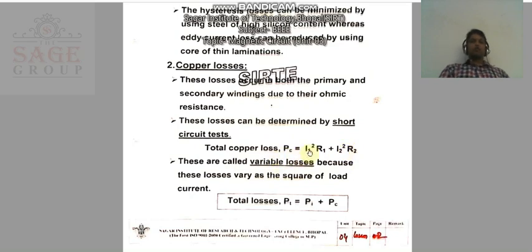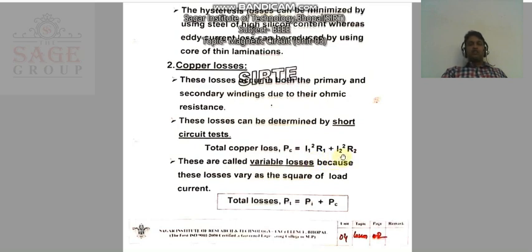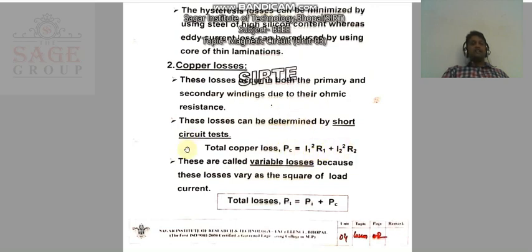The copper loss in the primary winding equals I1 squared times R1, where I1 is the primary current and R1 is the resistance of the primary winding. The copper loss in the secondary winding equals I2 squared times R2, where I2 is the secondary current and R2 is the resistance of the secondary winding. By adding the I²R of both windings, we can easily calculate the total copper loss of the transformer.